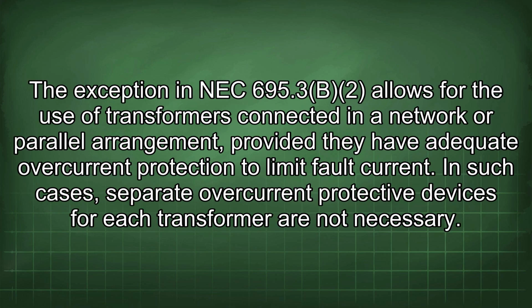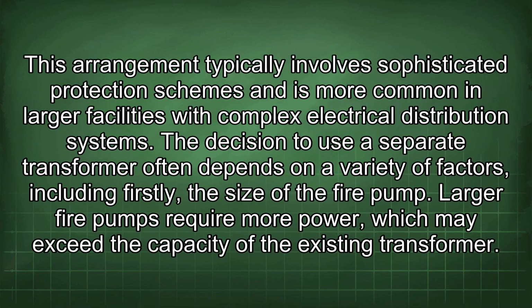The exception in NEC 695.3(B)(2) allows for the use of transformers connected in a network or parallel arrangement, provided they have adequate overcurrent protection to limit fault current. In such cases, separate overcurrent protective devices for each transformer are not necessary. This arrangement typically involves sophisticated protection schemes and is more common in larger facilities with complex electrical distribution systems.